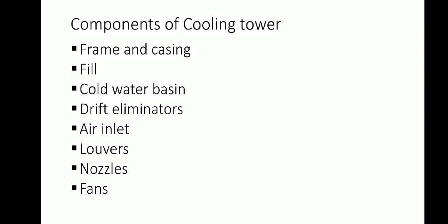Then the second part is fill. Most towers employ fills made up of plastic or wood to facilitate heat transfer by maximizing water and air contact. Fill can be either splash or film type. With splash fill, water falls over successive layers of horizontal splash bars, continuously breaking into smaller droplets while also wetting the fill surface. Plastic splash fill promotes better heat transfer than wood splash fill.